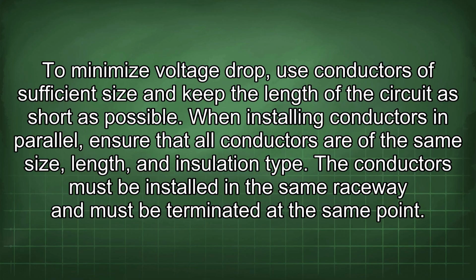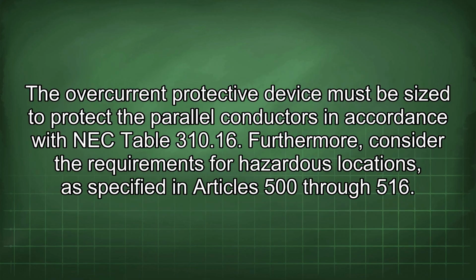When installing conductors in parallel, ensure that all conductors are of the same size, length, and insulation type. The conductors must be installed in the same raceway and must be terminated at the same point. The overcurrent protective device must be sized to protect the parallel conductors in accordance with NEC Table 310.16.